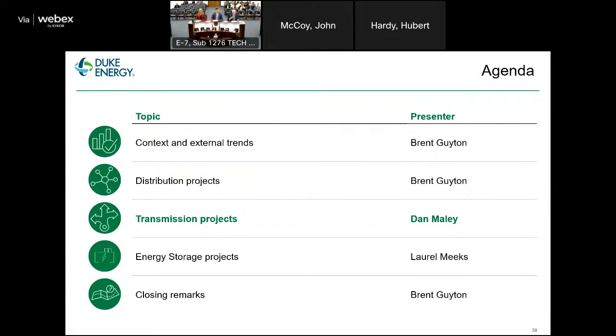So there's really two pieces, and I'll try two explanations here. One is the traditional controls that are on those traditional capacitors and regulators were built for one-way power flow. They don't know how to behave when we've got power flowing back the other direction. So the control upgrades - the equipment may be operating fine and may be in the right location to deal with those issues, but we have to have an upgraded control. So that's one piece of it.